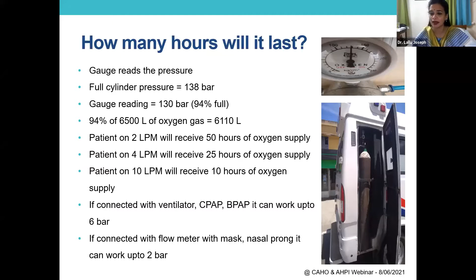If this particular cylinder is connected to a ventilator, it can work up to 6 bar because it is under pressure. If connected to a flow meter with mask, nasal prong, you can go up to 2 bar pressure, it can work.